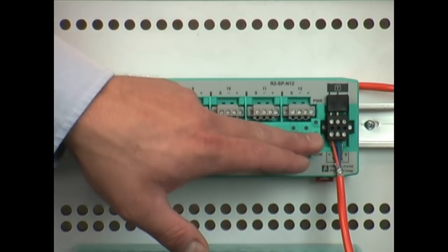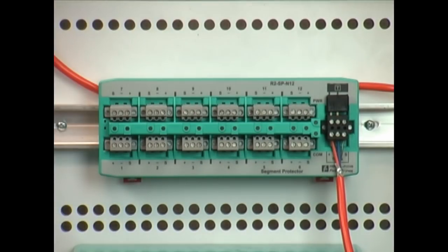Additionally you can daisy chain multiple segment protectors together using the trunk in and trunk out connection and these are used for safe area or Division 2 applications.